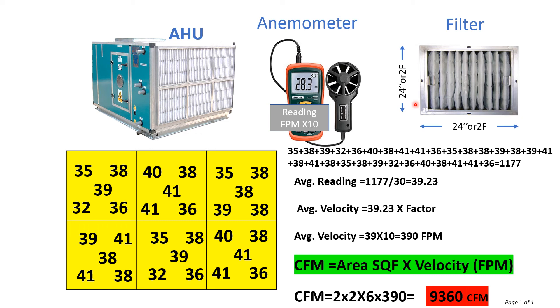For that particular AHU, we have calculated the total CFM. The actual design CFM of this AHU was 10,000, but currently we are receiving 9,360 CFM because of some filter choke-up and coil choke-ups.